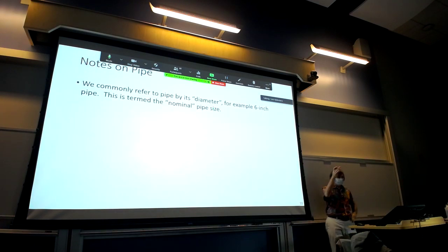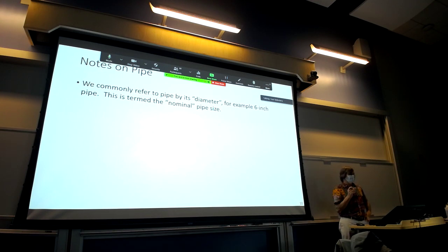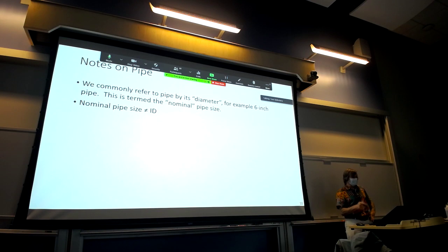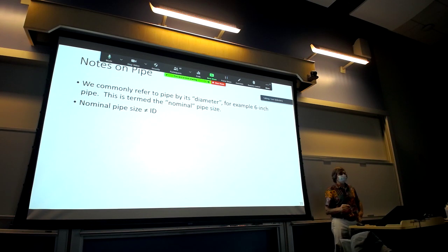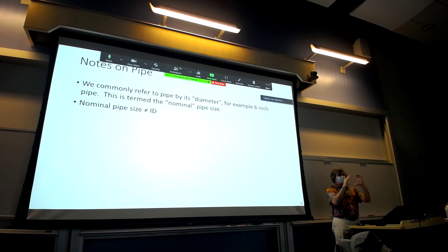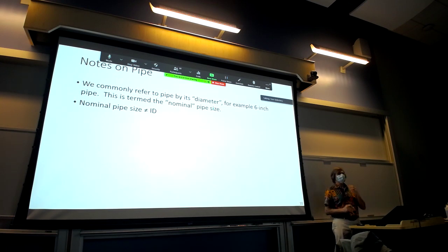Pipe is commonly referred to by its nominal pipe size — for example, 'six inch pipe.' However, the nominal pipe size is rarely the actual inside diameter. There are many different inside diameters for six-inch pipe depending on the material and pressure rating. The actual inside diameter is a function of the outside diameter and wall thickness, subject to manufacturing tolerances.